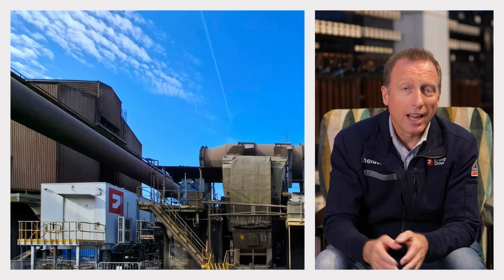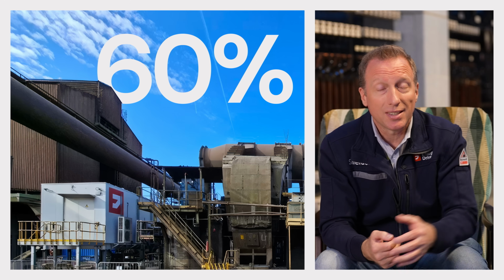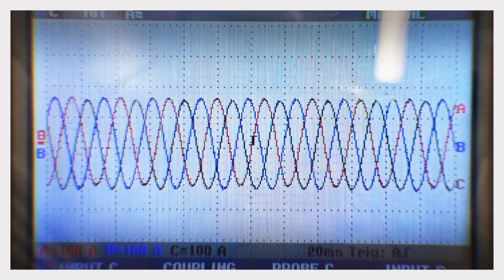I got to join my team in Spain on the final commissioning of a fume extraction system, this one actually producing 60% energy reduction. And I took these pictures of the output waveform. What I love about this picture is how smooth that waveform is, with a very, very low harmonic content. And it's impossible to dive into the detail of this in such a short clip. But the reality of it is less harmonics, less negative sequence harmonics. You don't have the backward spinning magnetic field inside the motor fighting the forward spinning fundamental field. Cooler motor, lower insulation temperature, better energy efficiency, and just a better system.